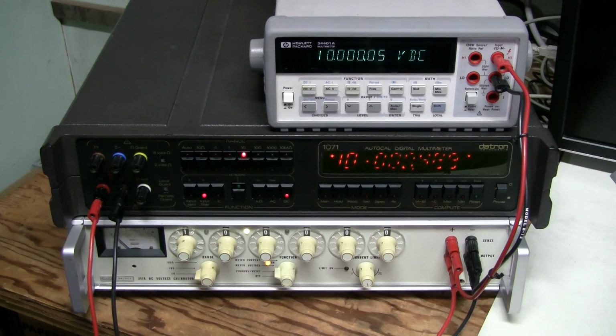I could not calibrate a few things, let's say high voltage AC, 100 volts and 1000 volt ranges. I could not find appropriate reference. Lower AC ranges I calibrated using my Hewlett-Packard function generator. I measured the output with the Hewlett-Packard meter and then transferred that reading into Datron. So now Datron pretty much should be as good as my Hewlett-Packard meter.